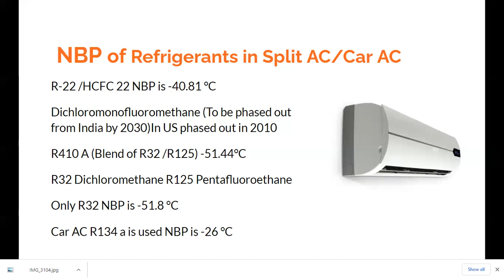Car air conditioning systems use R134A now, and the normal boiling point of the refrigerant in car AC is minus 26 degrees centigrade. So in air conditioning systems, if you want to generalize for small capacity systems, you will find that the refrigerant has a normal boiling point in the range of minus 26 to minus 40, minus 50 degrees centigrade. In chillers, different refrigerants are used depending upon the chiller, and that selection also depends upon the normal boiling point.